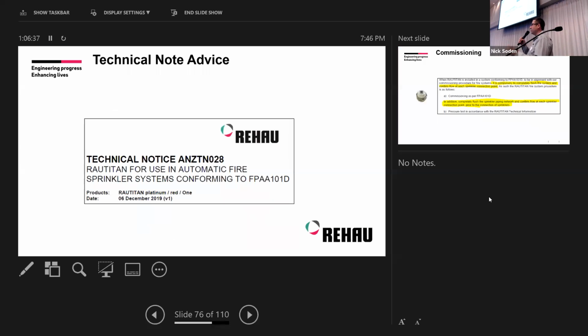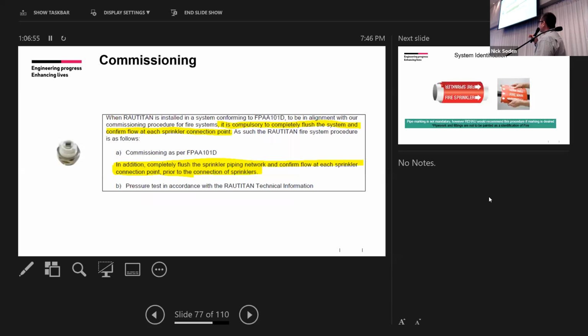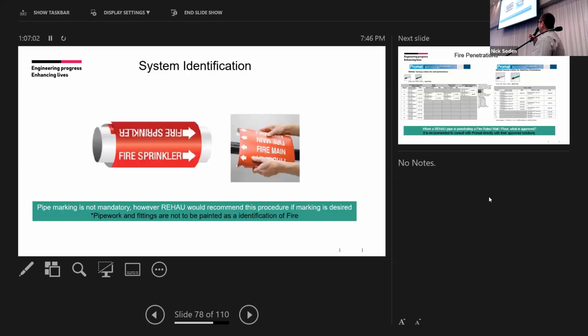Technical advice. With Rehau, we've got our technical information, our TI. However, for things outside those guidelines that come up, like fire sprinkler, we developed our TI, and then all of a sudden fire sprinkler popped up. We would do a separate technical note, which is a legal document that outlines some extra guidelines. With that came commissioning, so making sure you're bleeding all your sprinklers when you're doing your pressure test. Pipe marking: pipe marking is not mandatory in this area. However, Rehau recommends this procedure of utilising stickers, purely because it is the same pipe as a drinking water system. We've got green for rainwater, lilac for recycled, red for hot, and platinum for hot and cold. We just like to ensure that if you are installing a fire system, this is included as part of that.